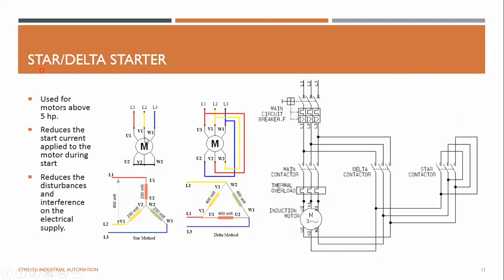All right, so this is the starter. In an induction motor, when you run it initially, a large current will be drawn. The delta connection allows higher torque, but a large current has to be drawn, and it could be damaging and could increase the maximum demand of the power supply, and sometimes these main circuit breakers could trigger and turn it off.